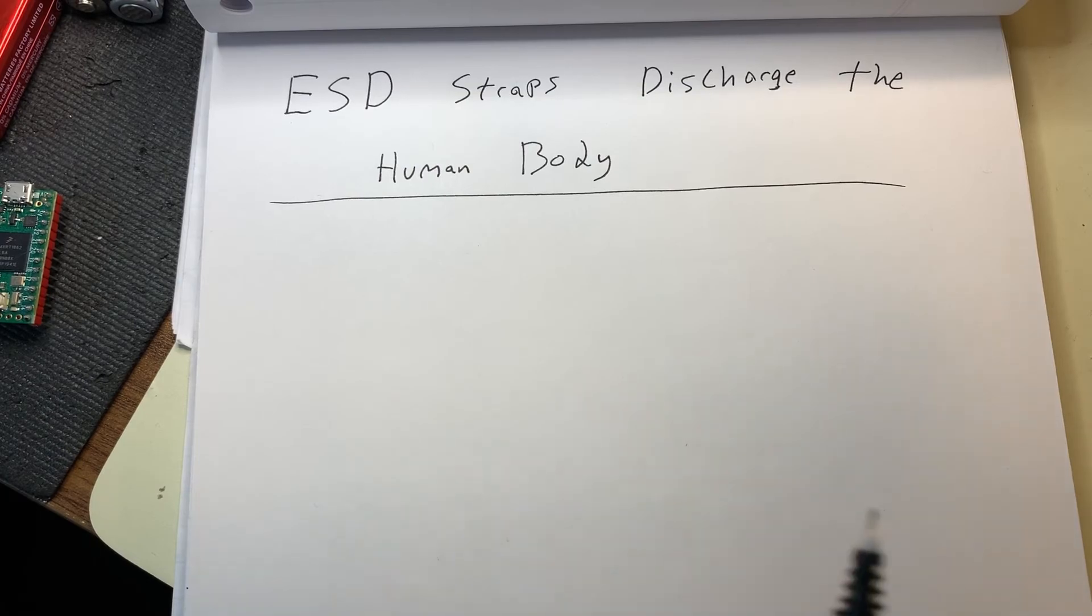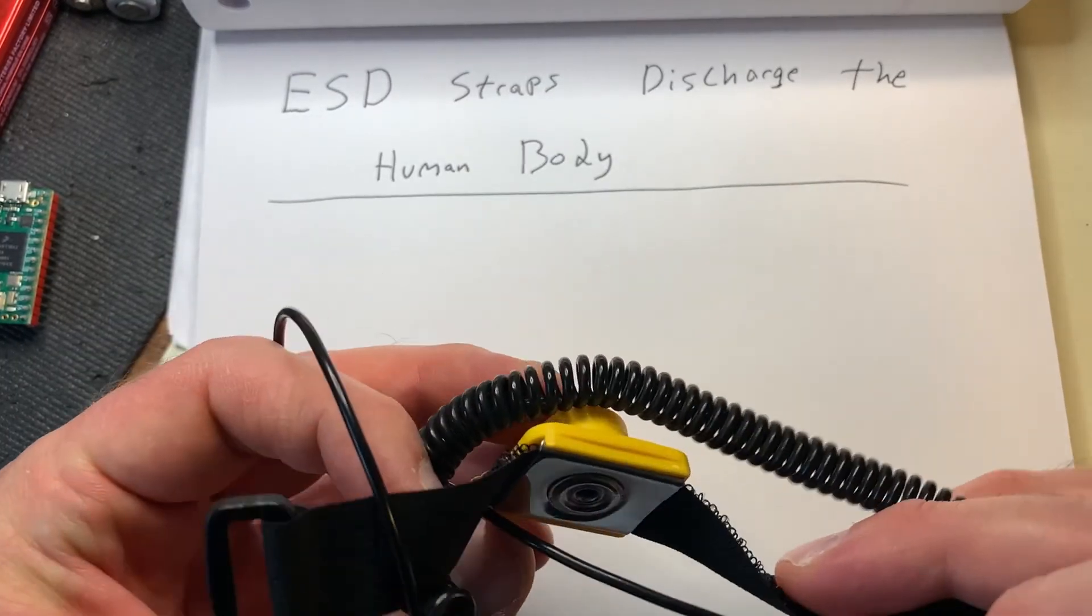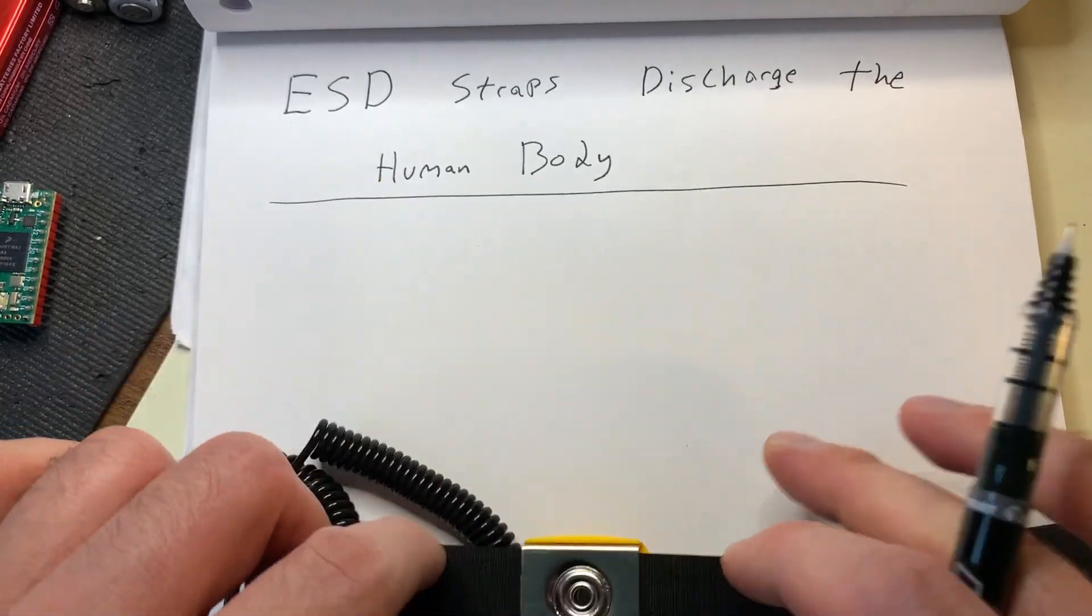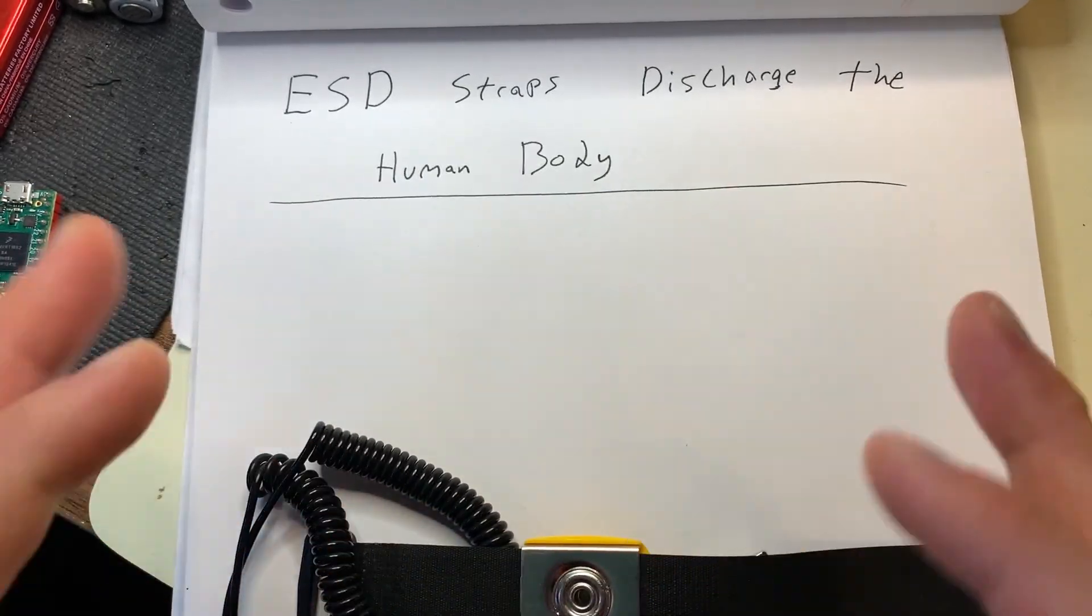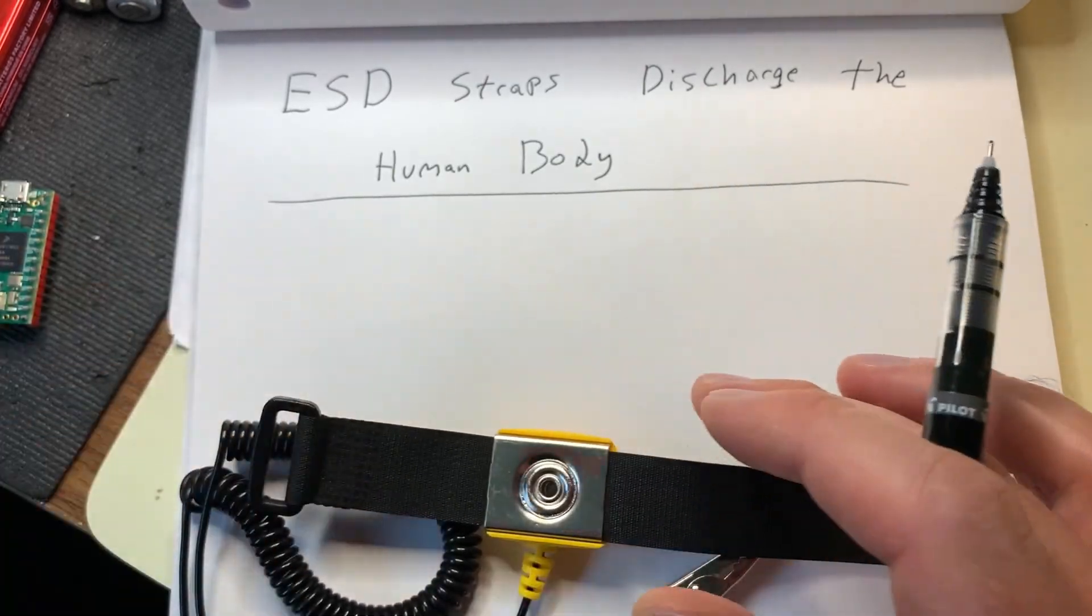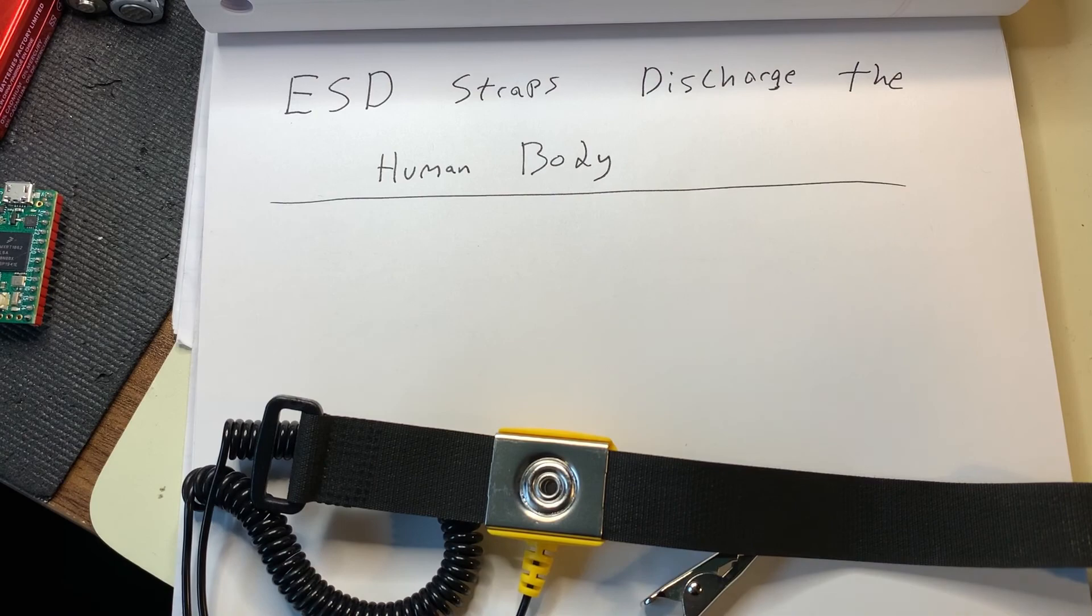So this is where ESD straps really come into play. Not only for the safety it provides you, but the safety it provides for your device that you're working on. Because effectively, the wrist strap's job is to discharge a human body's capacitance.